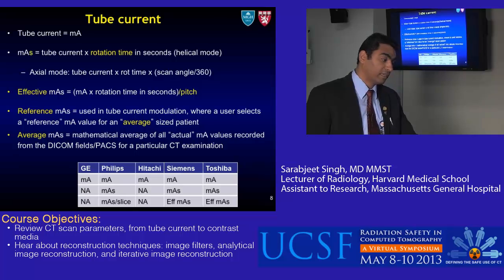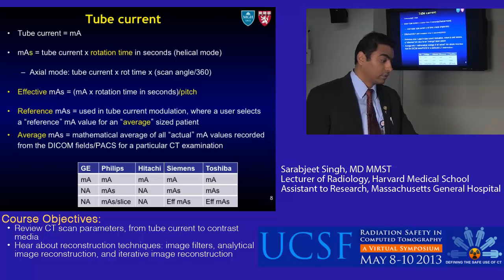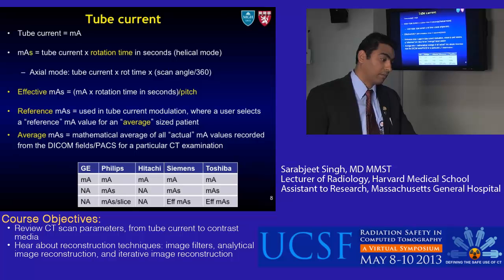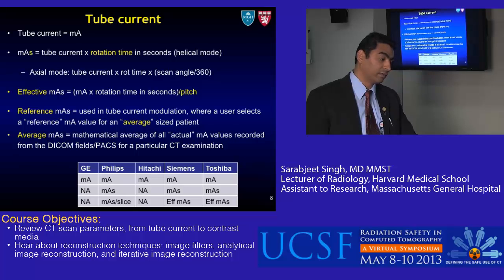Effective mAs is calculated by taking mAs and dividing it by pitch. Reference mAs is a different term used in tube current modulation by one scanner manufacturer, where the user selects a reference mA for an average-size patient — so it differs from effective mAs. Average mAs is the mathematical average of all actual mA values, which can be recorded from the DICOM fields or PACS for a particular CT examination.